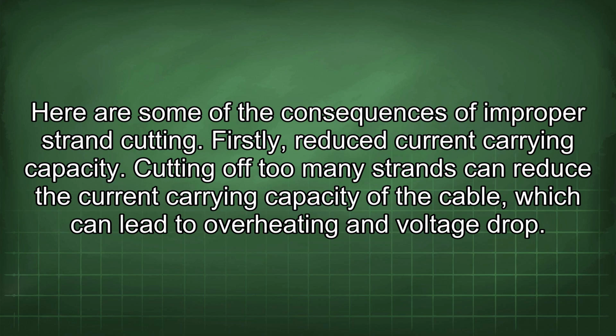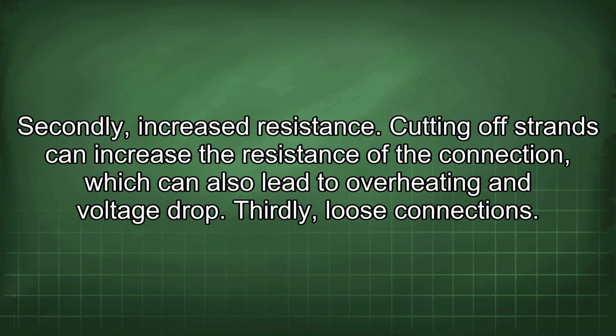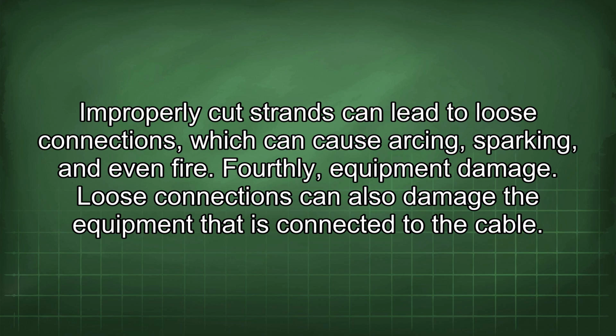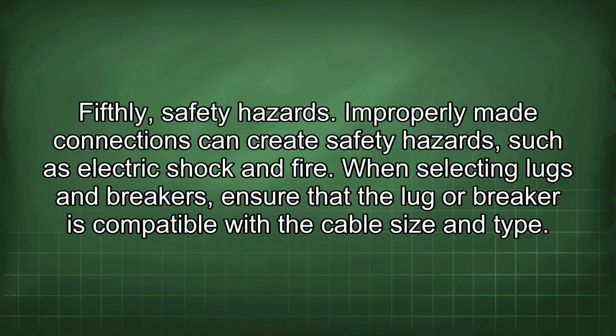voltage drop. Secondly, increased resistance. Cutting off strands can increase the resistance of the connection, which can also lead to overheating and voltage drop. Thirdly, loose connections. Improperly cut strands can lead to loose connections, which can cause arcing, sparking, and even fire. Fourthly, equipment damage. Loose connections can also damage the equipment that is connected to the cable. Fifthly, safety hazards. Improperly made connections can create safety hazards, such as electric shock and fire.